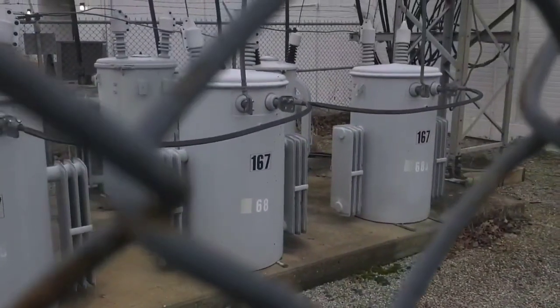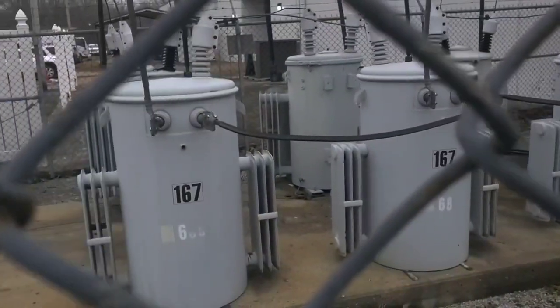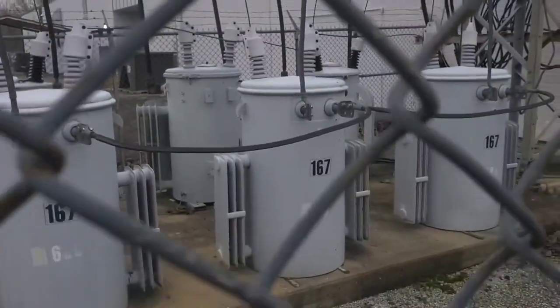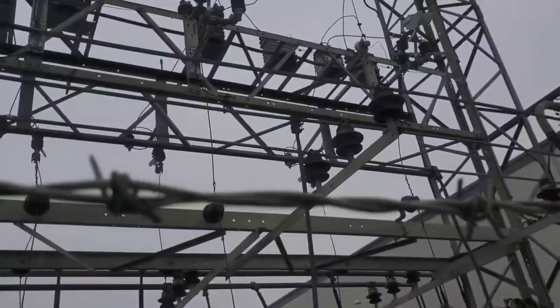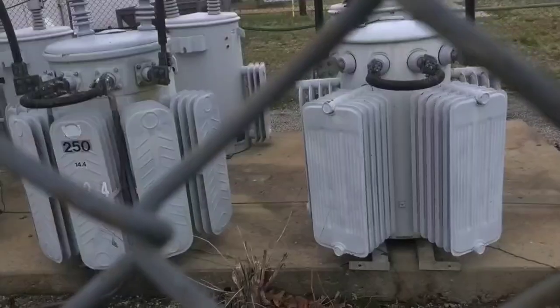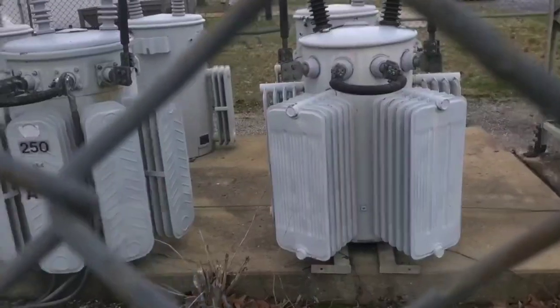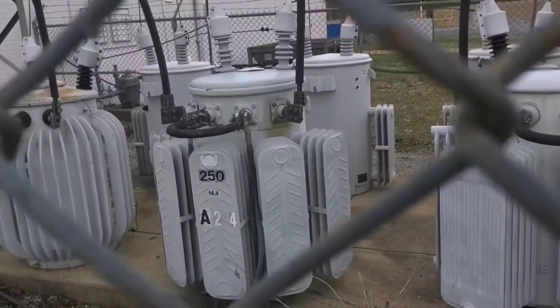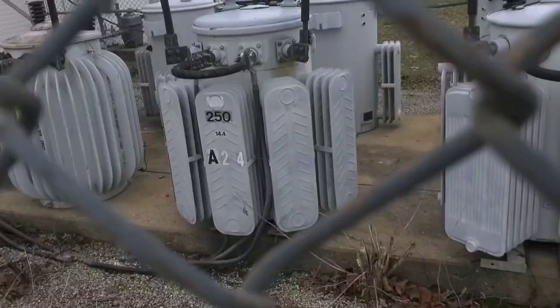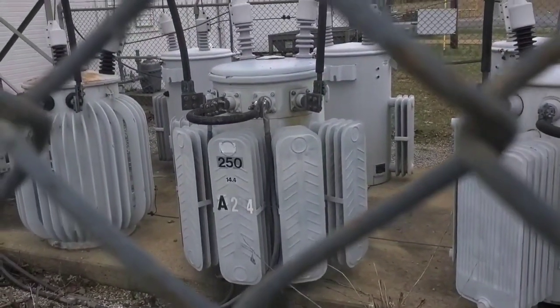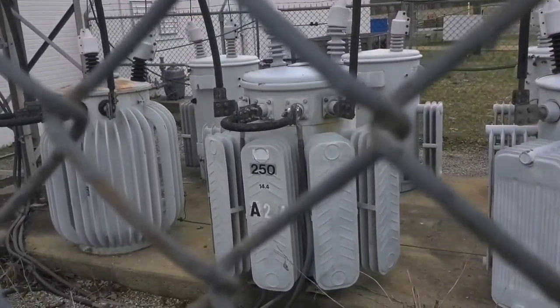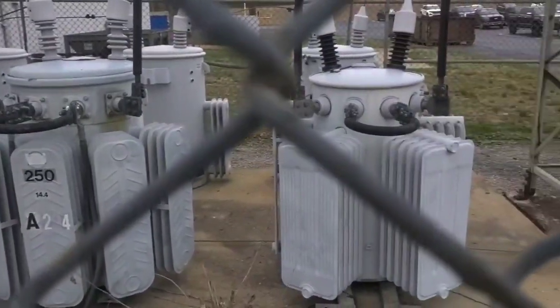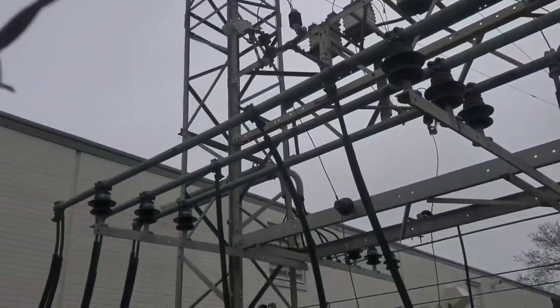Just basic stuff. This side is the 480 volt side. You see how all 3 of those transformers have one terminal tied together? That's a Y configuration. 480 is a Y configuration. The 240 side is Delta, and the dead giveaway is the middle transformer there has the ground wires connected to its little center jumper. So that's the center tap ground of the Delta. The bigger bus bars over here kind of gives away which voltage is which.